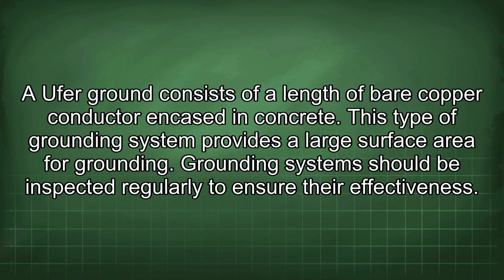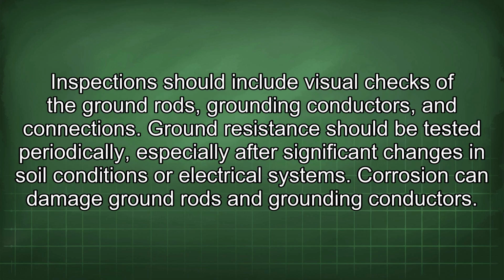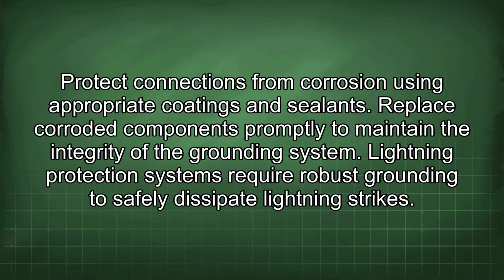Grounding systems should be inspected regularly to ensure their effectiveness. Inspections should include visual checks of the ground rods, grounding conductors, and connections. Ground resistance should be tested periodically, especially after significant changes in soil conditions or electrical systems. Corrosion can damage ground rods and grounding conductors. Protect connections from corrosion using appropriate coatings and sealants.